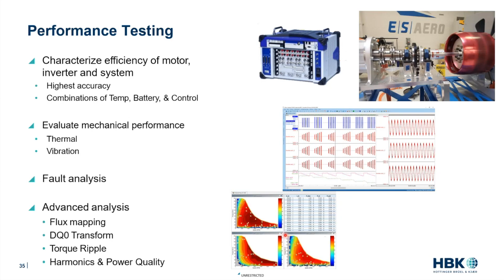One of the additional benefits that we have is we use an algorithm called cycle detect, where we can actually track the fundamental frequency as speed is changing, which means if you are executing a flight sequence, as your motor's speeding up, we can give you a really good power measurement as you're going through that flight sequence.